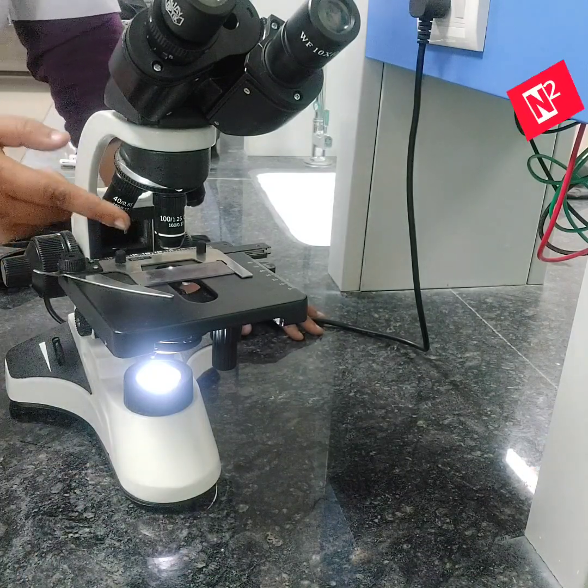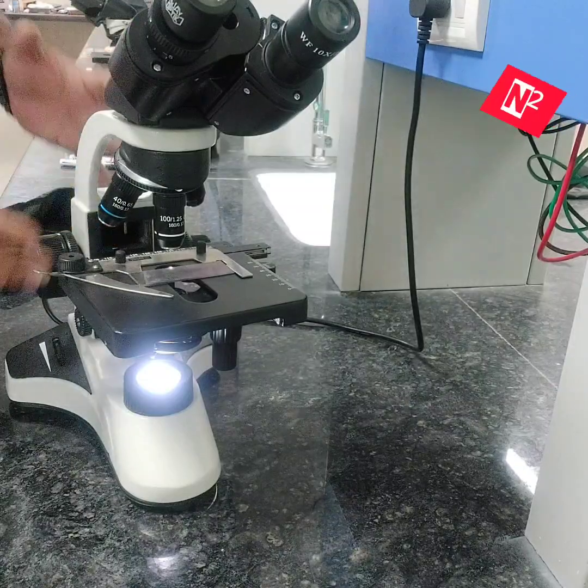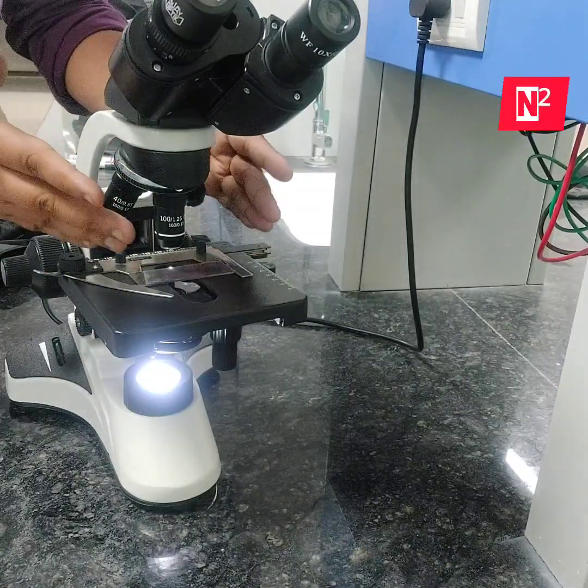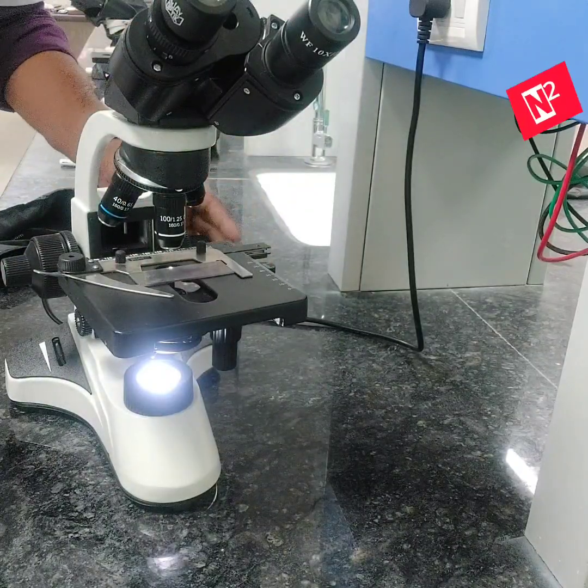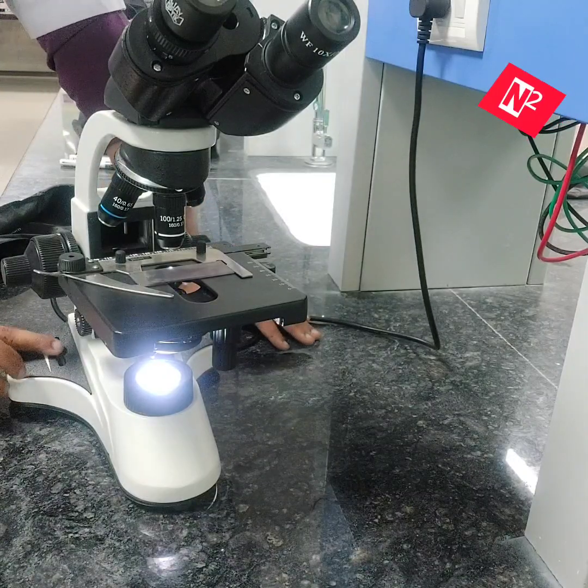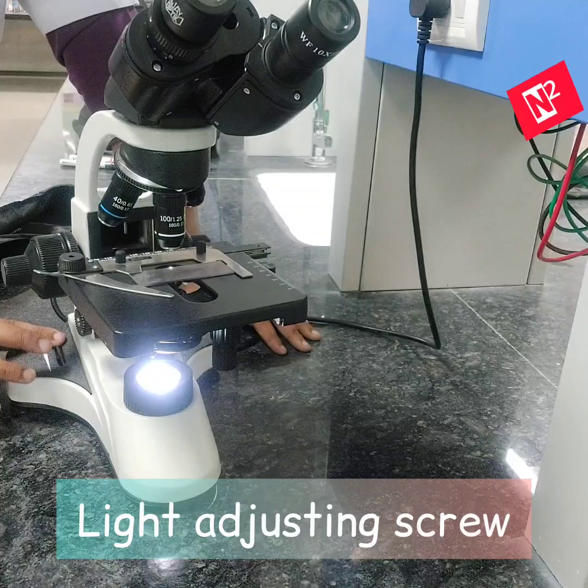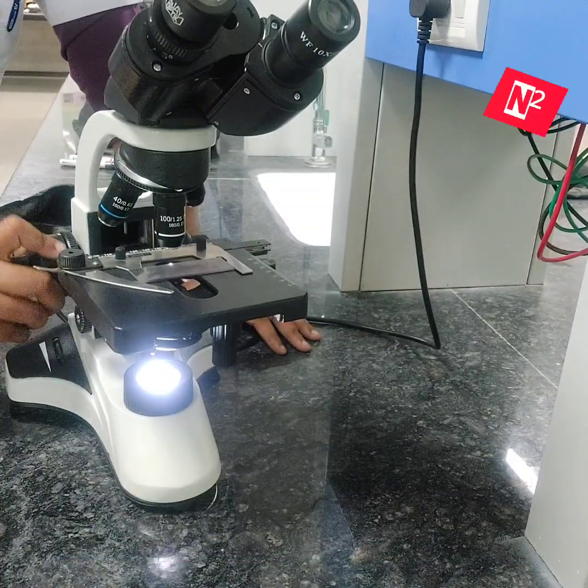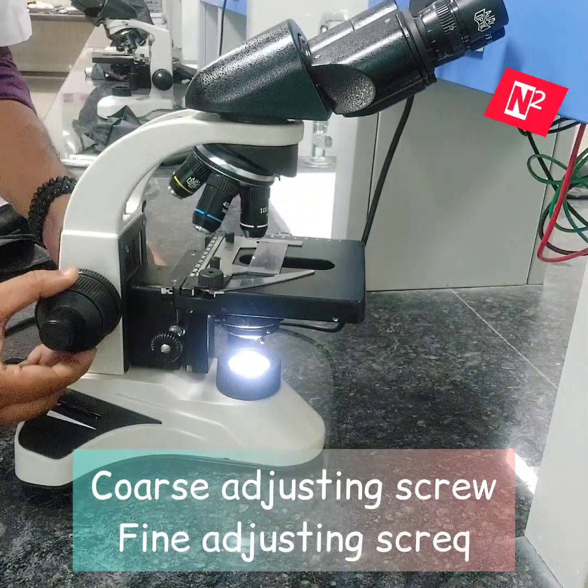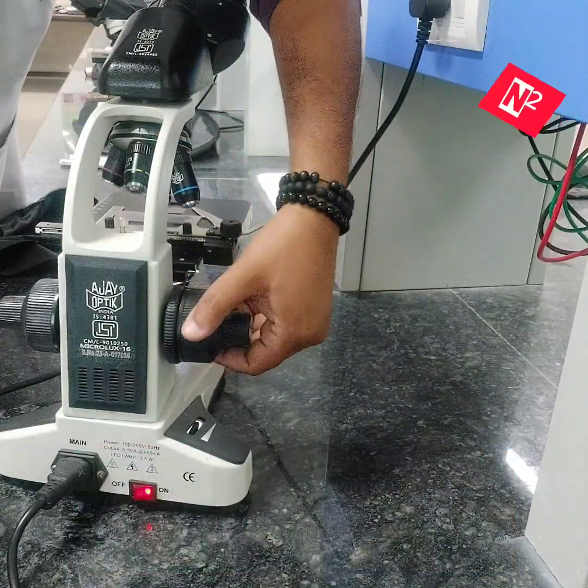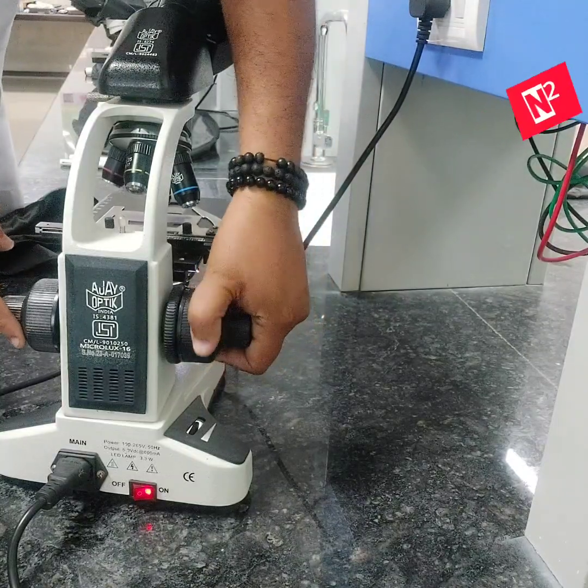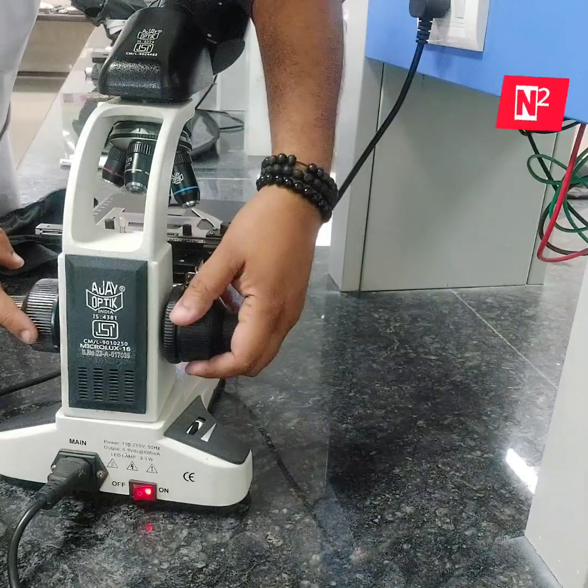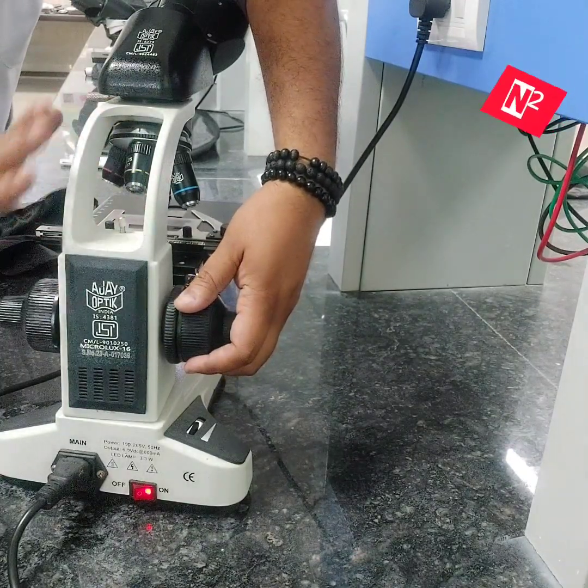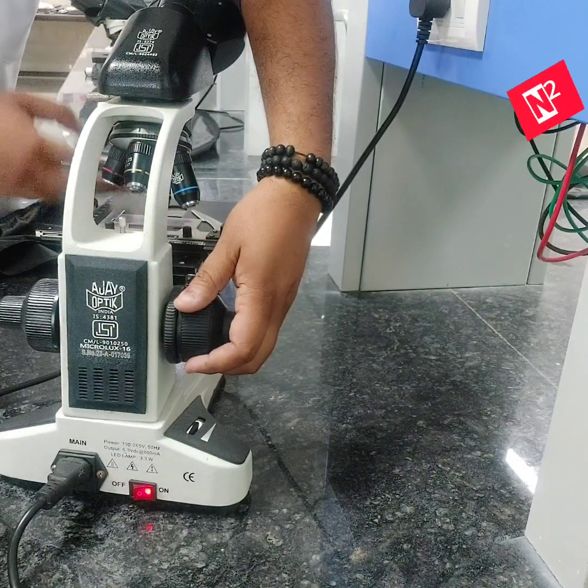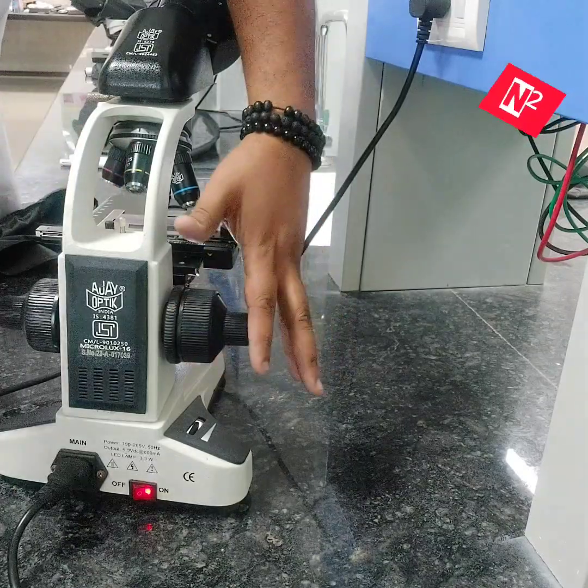Now, while using the low power and high power settings, we have to adjust the image, adjust the stage and the body tube. So how do we adjust? There are some adjusting systems of this microscope. First and foremost is the regulator, which regulates the light intensity coming from the artificial source of light. The second adjusters are on either side of the pillar: you can see circular screws, one bigger and one smaller. While I'm moving this screw, the other screw also automatically moves. That's very convenient, so that if you're adjusting the microscope with one hand, your other hand becomes free to do other work like adjusting the stage or moving the slot of the objective lens.